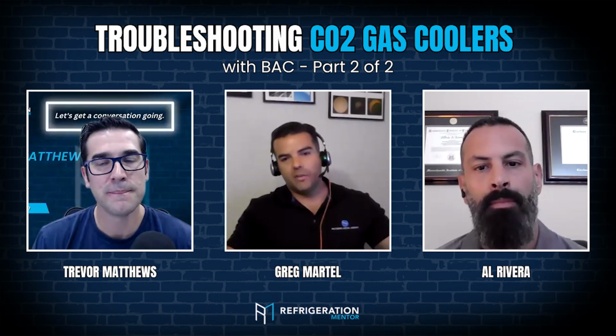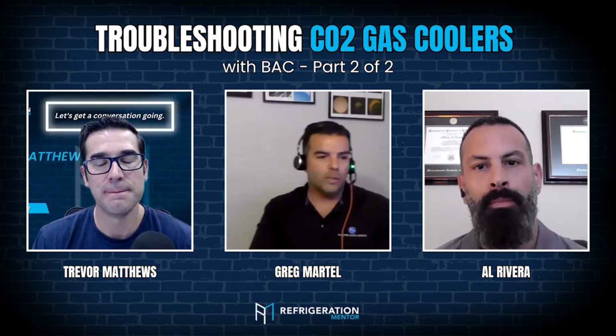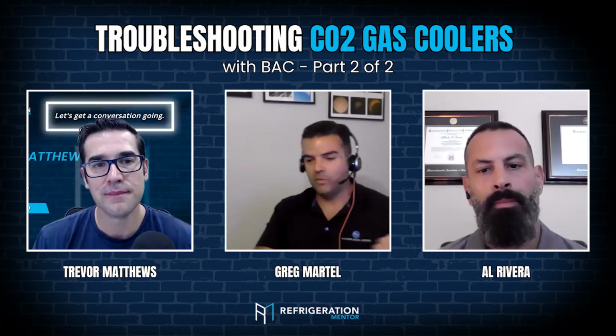Obviously, like I was saying, now you only run water if your fan speed is above 90% for over 10 seconds, 15 seconds, something like that. So that works awesome in units that are slightly oversized, because I know it's opposite to what I said before, but if you have more dry capacity, obviously you can sustain your set points for longer. So it depends on a lot of things, and it depends on environment and cost of water, obviously.